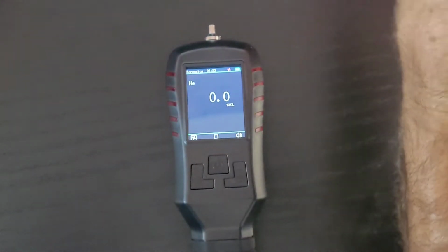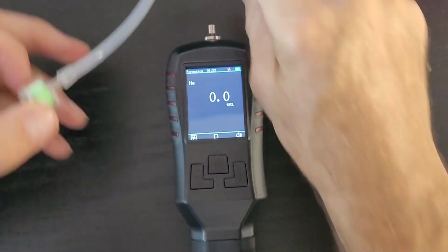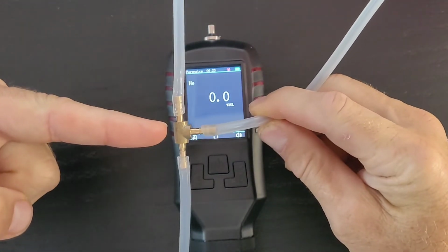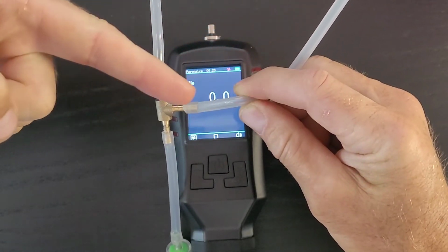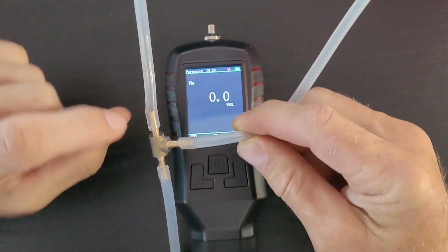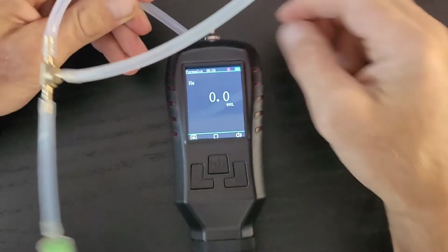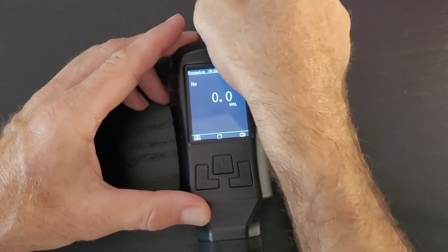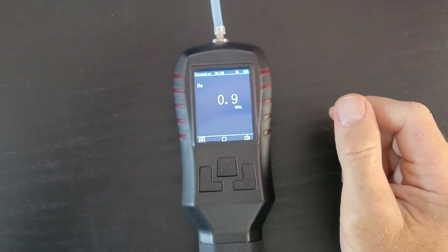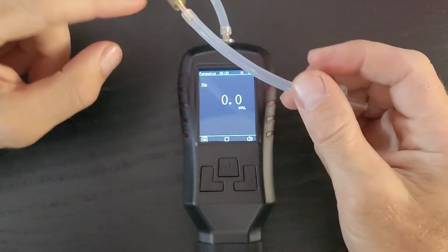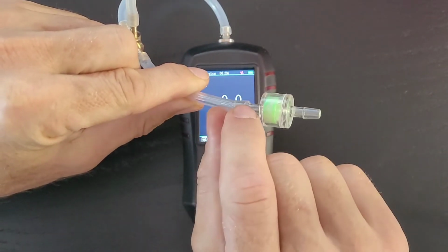Second step is you need your source. Your gas calibration, in this case we're using 100% helium, you need your T-piece that splits the source. The source is coming here, okay, 100% helium, and then it gets split in two channels. One channel is just an open line, and this guy will go to the analyzer. So let's plug that in. It's got some residual helium there, folks. It's off, but it's going to clean out the line. And the other end of this T-piece is going to a particle filter. It's just creating a bit of pressure.